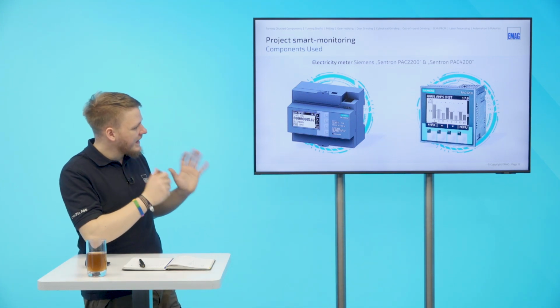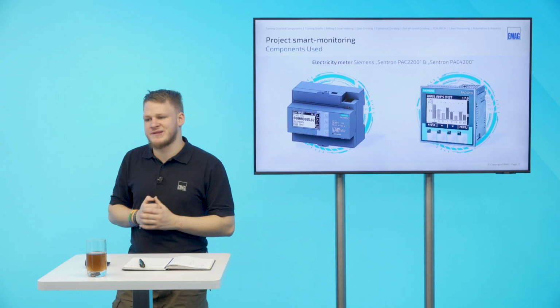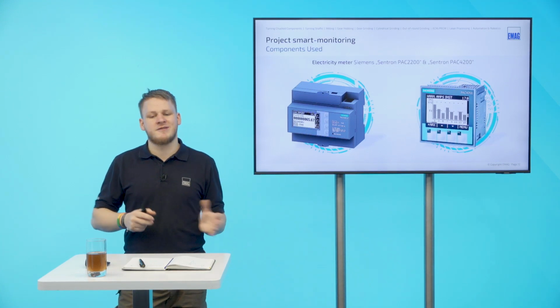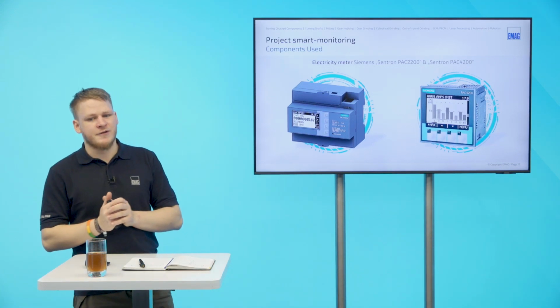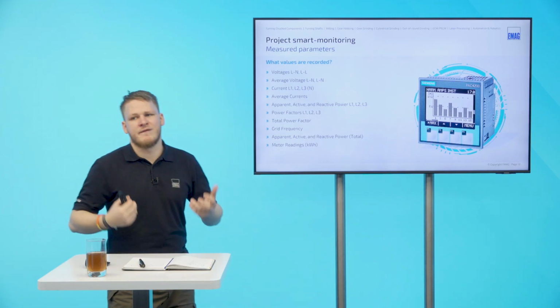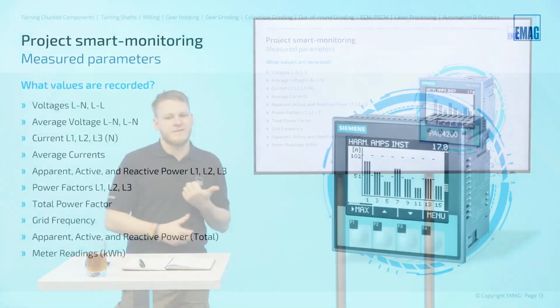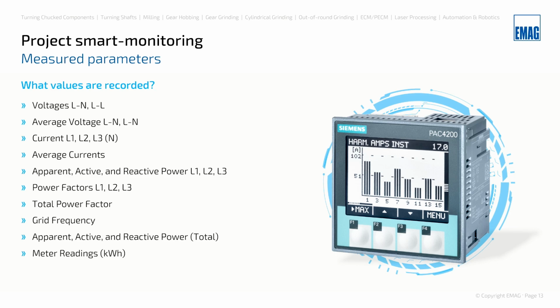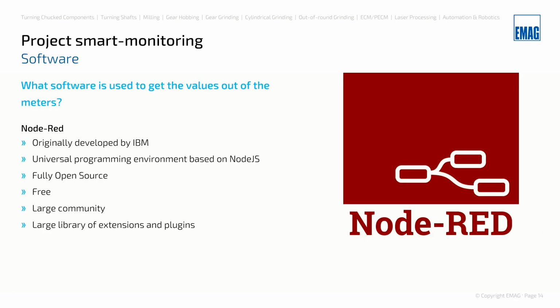These meters actually have a Modbus TCP interface that we use to later read out the data. But at first, we want to see what kind of values we even get. That starts with classic meanings such as voltages, currents, apparent active and reactive powers, as well as power factors, the grid frequency, and the meter readings, telling us how many kilowatt hours have passed through the meter, so we can do hourly or daily analysis too of total meter readings.